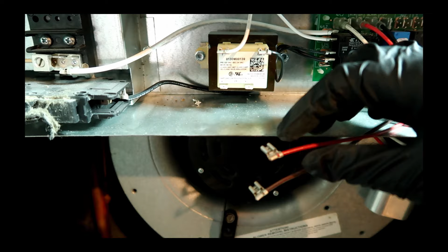I'm going to pull these low voltage wires off, and I'm going to see if 24 volts is coming out of here. And if it's not, then I think this is going to be my culprit. But I'm going to do the outside contactor first. Just trying to do a little process of elimination here. I got to turn the breaker back on to power up the transformer. Alright, let me set the meter to voltage.